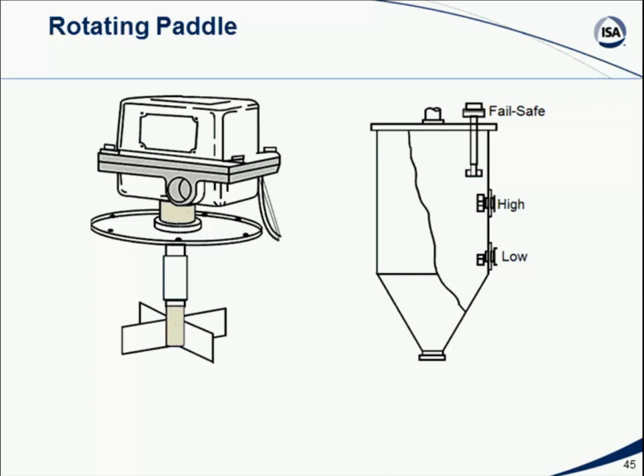It's going to pile up in a bin. And in many cases, I don't really care about the exact level. What I care about is whether the material in the bin has dropped down to a certain point where I need to make sure to go fill it again, or whether we've gone up to a certain point where we can't put any more in it. So sometimes all I really care about in a bin situation is point level measurement. In other words, is the level below here, is the level above there?